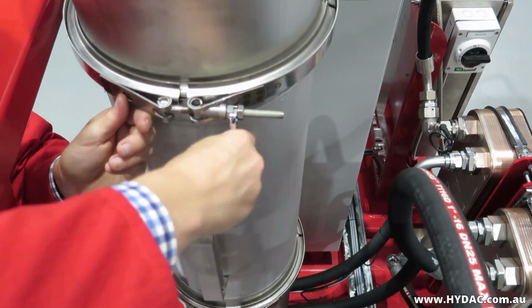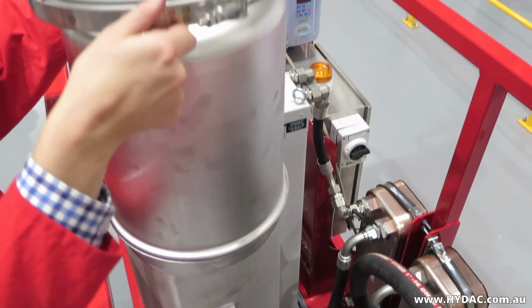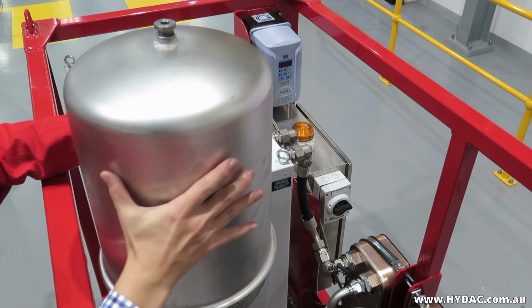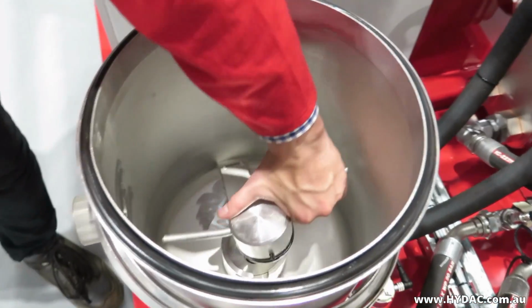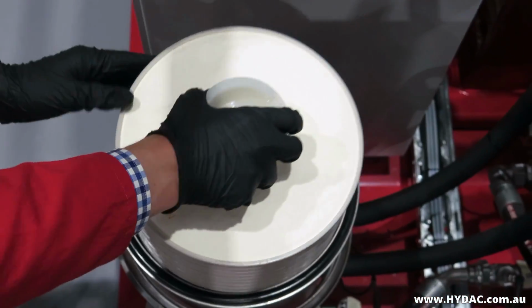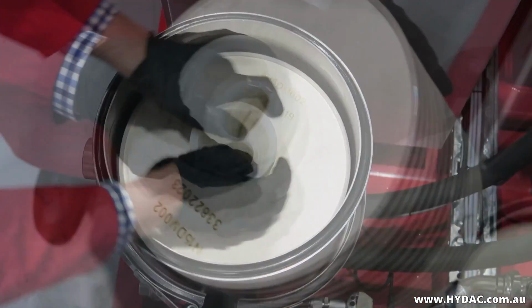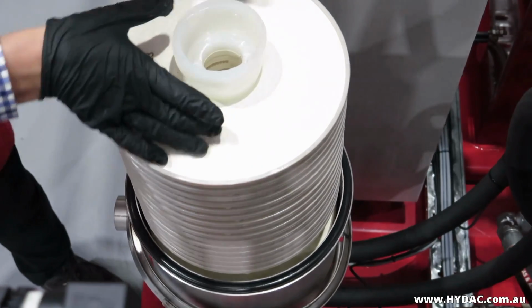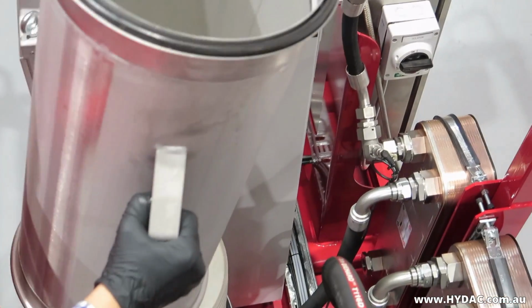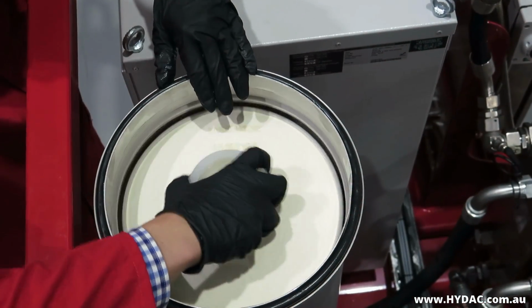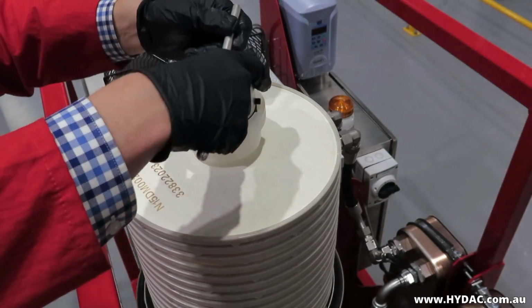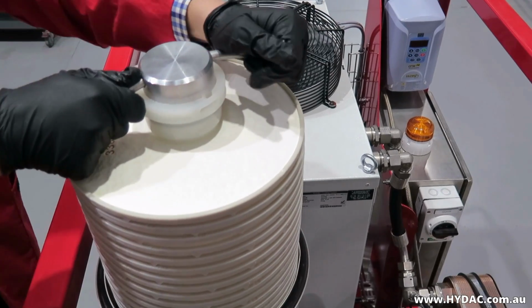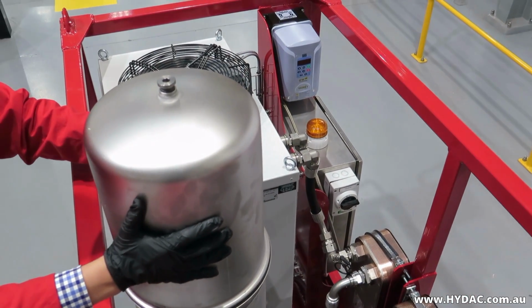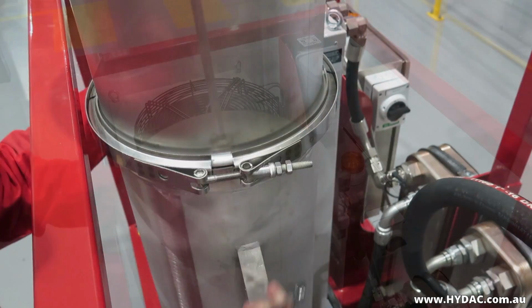Loosen the lower clamps. The housing may be split into 2 sections by loosening the upper clamp. This will reduce weight on each section. Lift up the housing cover. Remove the locking cap. Put the element into position. This is the same procedure as for changing the element. Replace the locking cap once the filters are installed. This will ensure that the oil is filtered. Replace the housing cover, clamps, and tighten the vent screw.